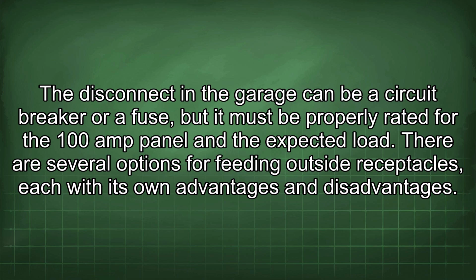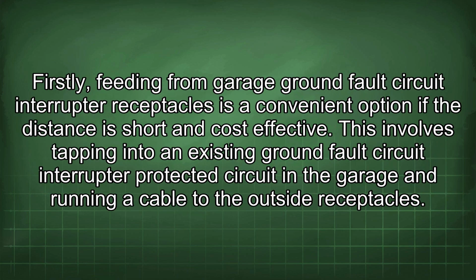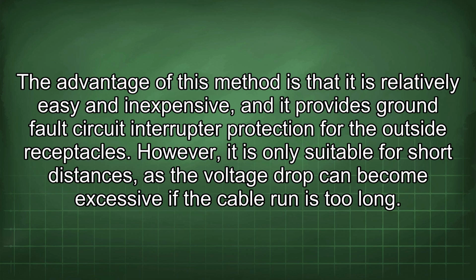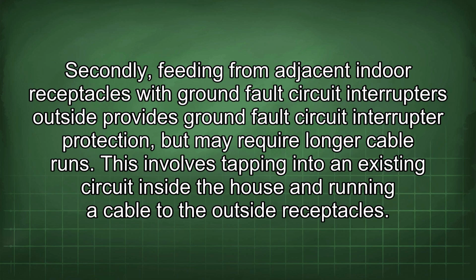There are several options for feeding outside receptacles, each with its own advantages and disadvantages. Firstly, feeding from garage ground fault circuit interrupter receptacles is a convenient option if the distance is short and cost-effective. This involves tapping into an existing ground fault circuit interrupter protected circuit in the garage and running a cable to the outside receptacles. The advantage of this method is that it is relatively easy and inexpensive, and it provides ground fault circuit interrupter protection for the outside receptacles. However, it is only suitable for short distances, as the voltage drop can become excessive if the cable run is too long.